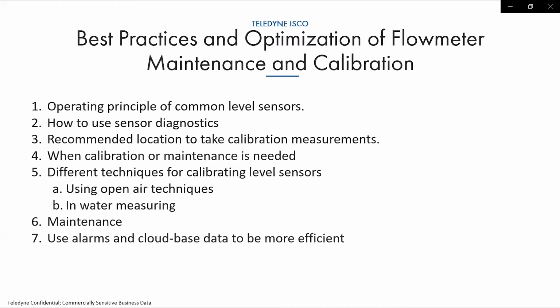We'll talk about the recommended locations to take your level measurements on weirs and flumes. We'll discuss when calibration or maintenance is needed. And I'll talk about the different techniques for calibrating level sensors, such as using open air techniques or measuring in the water. And then as I go through this, I'll discuss different maintenance items that will help you optimize your flow applications. And finally, I'll finish up with using alarms and cloud-based data to be more efficient.